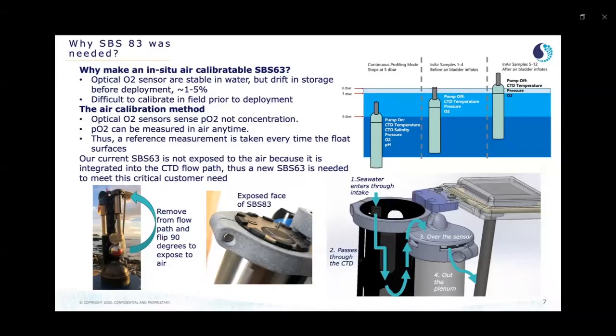So what is the in-air calibration method? Well, optical oxygen sensors sense PO2, or the partial pressure of oxygen, and not concentration. You can use this partial pressure of oxygen to take a reference measurement for an oxygen sensor any time in the air. So anytime the float surfaces, you can take a reference measurement.